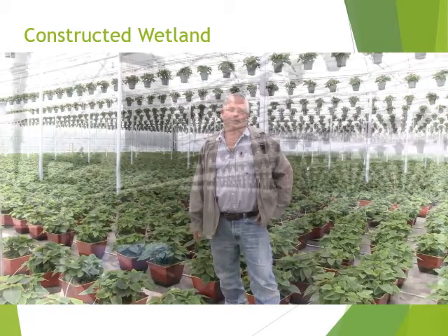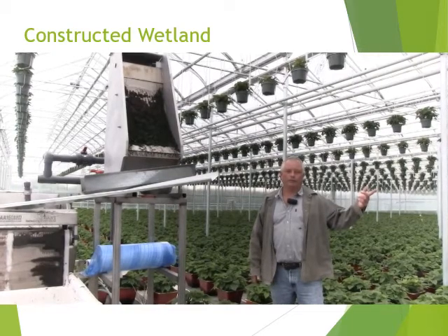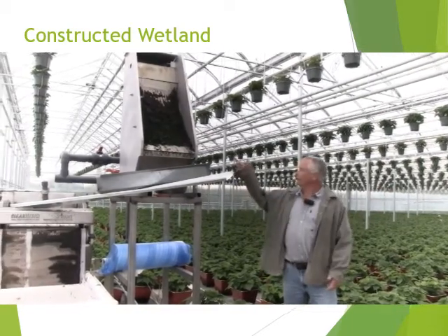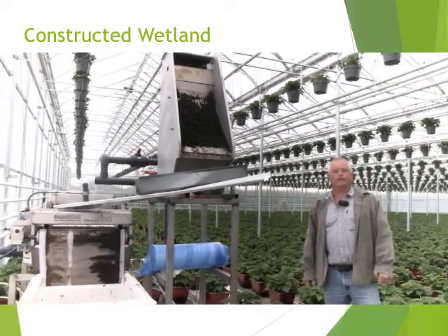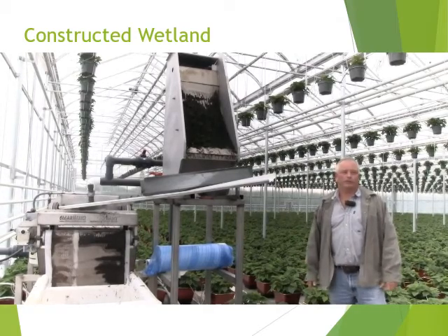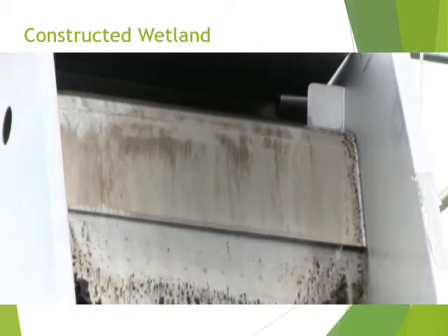All of the irrigation leachate water is collected in a sump that's located out of doors. The water from this sump is then applied into this coarse screen filter. This screen filter removes all of the peat moss and some of the larger particles prior to its application to the constructed wetland. The water from the sump is poured onto the coarse screen filter.